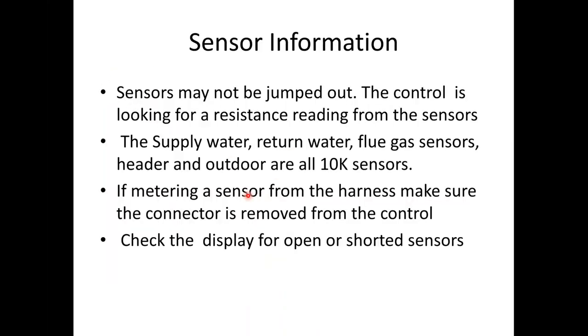Our sensors are not able to be jumped out. Can't jump them. They're looking for a resistance, a constant resistance. Supply and return water temperatures are all going to be 10K. If you're metering it, I suggest meter it right from the harness. Again, one of the disadvantages to not being there in person.